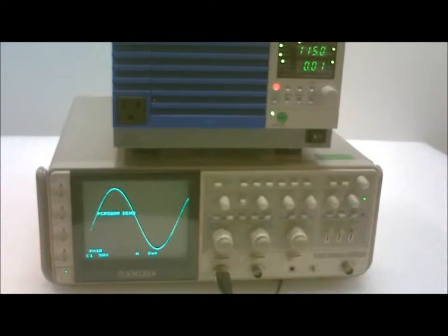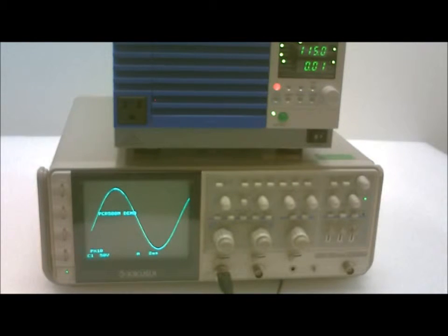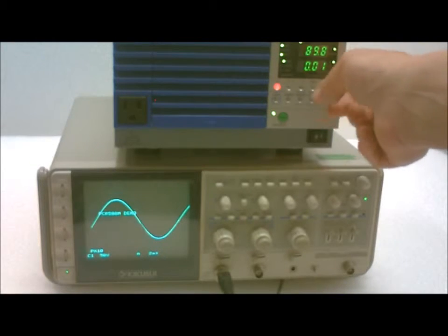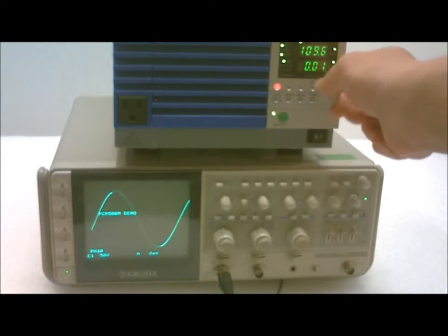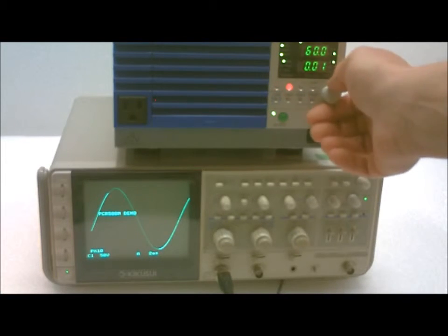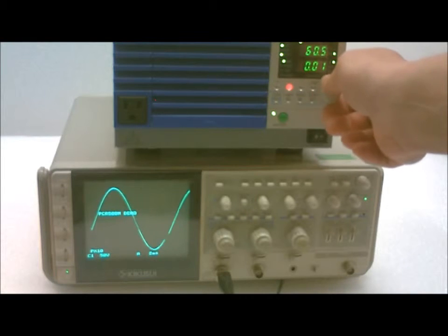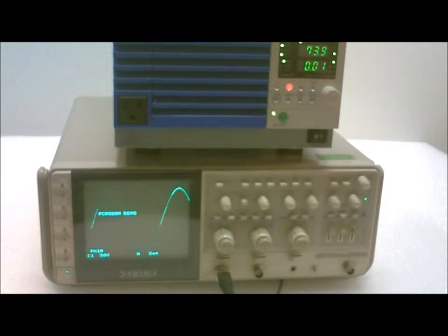Now we can also vary the output voltage and frequency around these levels for margin testing. These can be seen changing on the oscilloscope. Now we are going to show the output voltage being set to 115V at 400Hz.